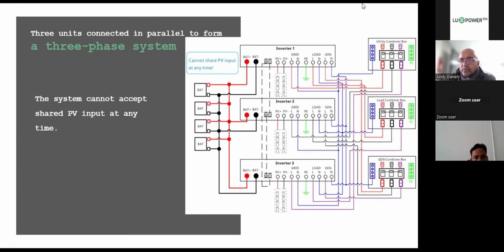This is how you will know on a three-phase installation that you've got a good three-phase: if you take your multimeter and measure between the inverter 1 live and inverter 2 live, you should get 400 volts. Between 2 and 3, you should get 400 between live and live, and between 1 and 3, you should get 400, and then live to neutral is 230. Any live to neutral will give you 230, and live to live or phase to phase is 400. And that's our system output in off-grid mode. In on-grid, it'll obviously do exactly what the grid is doing, so that will fluctuate. But in pure sine wave, it'll be 400.